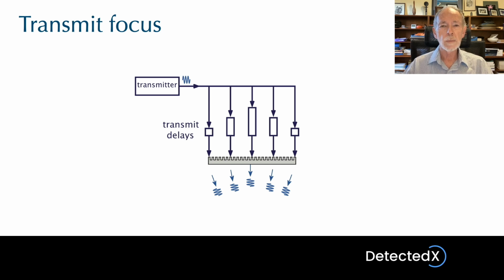There's a transmitter package of electronics which creates the actual transmit pulse. This is then connected to each of the elements that is being used via a set of delays. So we have delays, electronic delays, which are interposed between the transmitter and the elements. I've shown just 6 here to keep this diagram relatively simple, but in fact there would be a delay for every single transducer element that was being used. So kind of going back to the previous slide, we would have 128 different delays for that particular case.